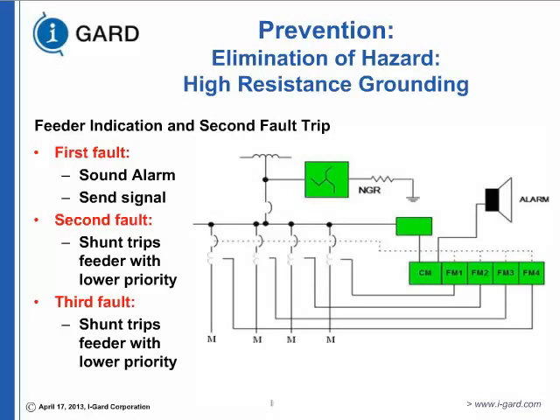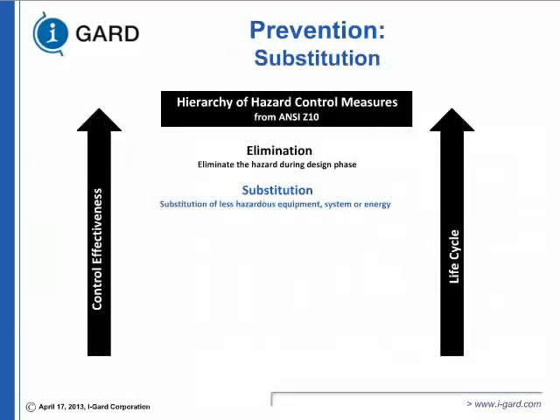Now technology is available that you can monitor all your feeders and assign priority to them. For example, if you have a lube oil pump that is supporting a large motor generator, you can assign it the highest priority. If a second fault comes, which is of lower priority, it will be automatically tripped. So you'll never have two faults at the same time. If a third fault comes in, it will be treated as a second fault. So priority-wise, the lower priority system will trip, giving you extra advantage. That is very important because some equipment you may not want to lose till the process shuts down.